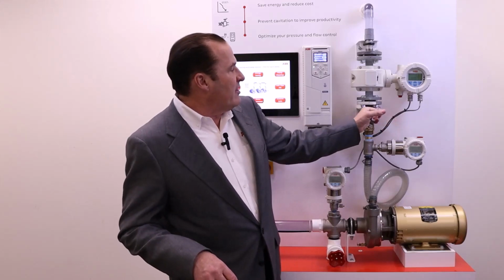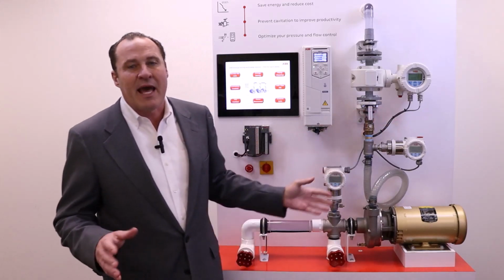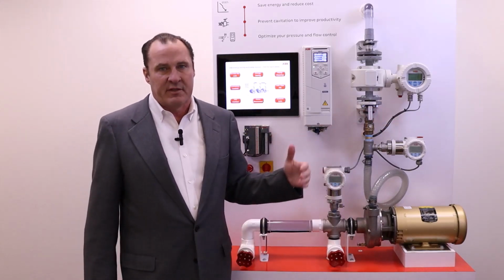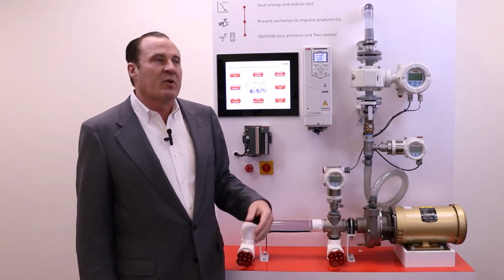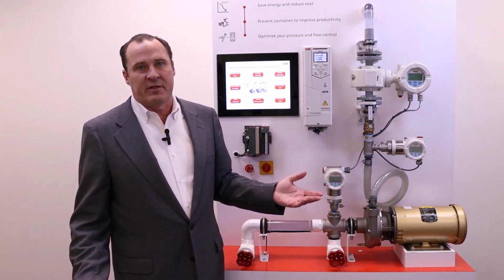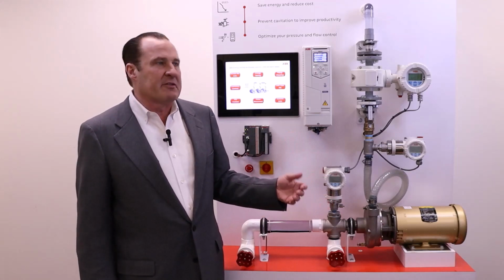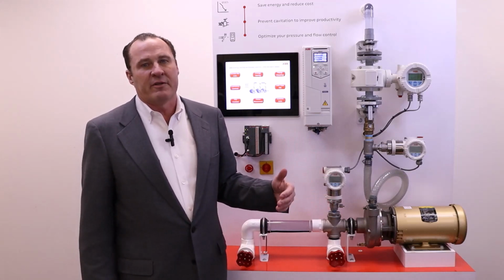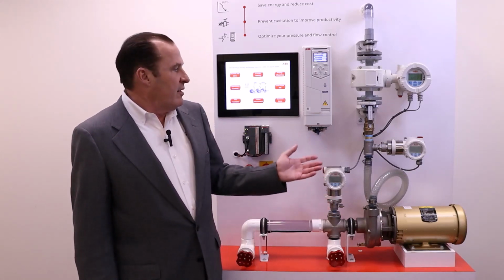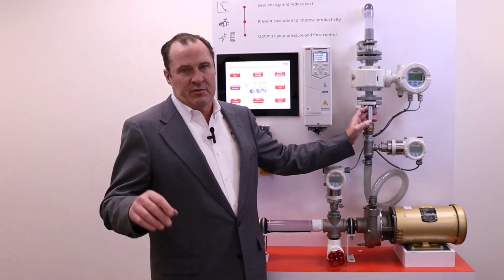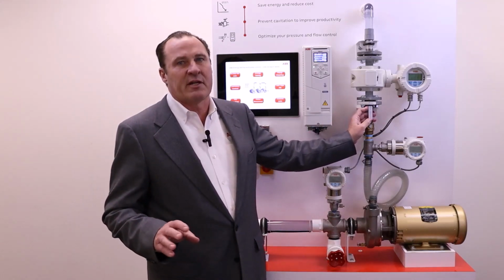So no matter what, we have one data point. And at the top data point, the 10th data point, that's going to be 38.46 for flow, gallons per minute. So what we need to do is take like 38 gallons per minute, divide it by 9. That gives our first data point of 4.22. That would be data point 2. So let's start our system out. Let's get our data points.